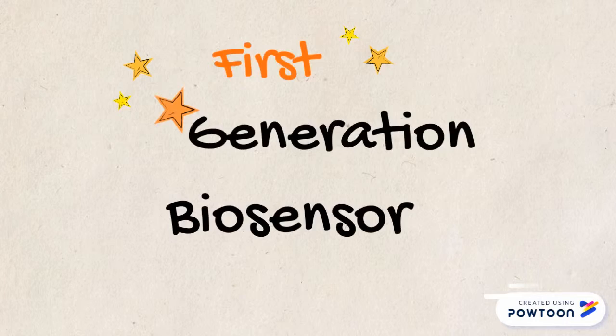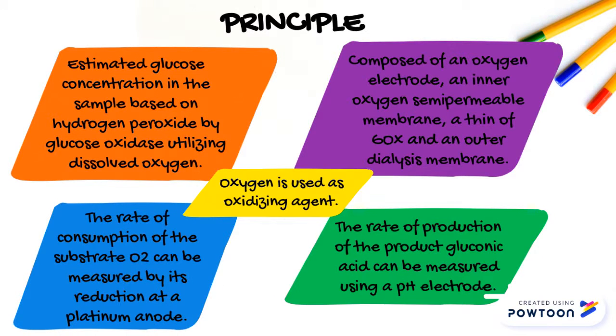First generation biosensor: the estimated glucose concentration in the sample is based on hydrogen peroxide produced by glucose oxidase utilizing dissolved oxygen. The biosensor is composed of an oxygen electrode, an inner oxygen semipermeable membrane, glucose oxidase, and an outer dialysis membrane. Oxygen is used as the oxidizing agent. The rate of consumption of the substrate can be measured by its reduction at a platinum anode. The rate of production of gluconic acid can be measured using a pH electrode.